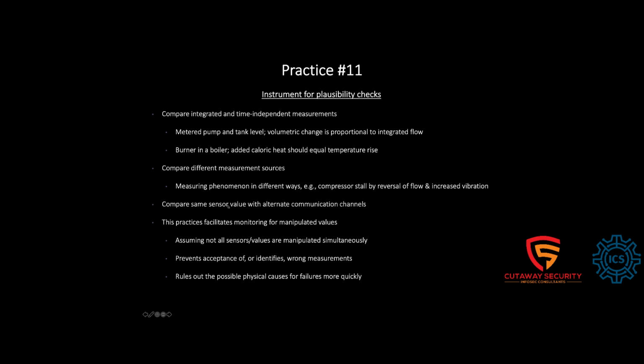So a couple of examples. One, comparing integrated and time independent measurements. If you have a tank and there's a flow meter for the tank level increase, and you've got a level meter on the tank as well, the volumetric change from the flow meter should be proportional to the volumetric change in the tank, right? So those two things are related.